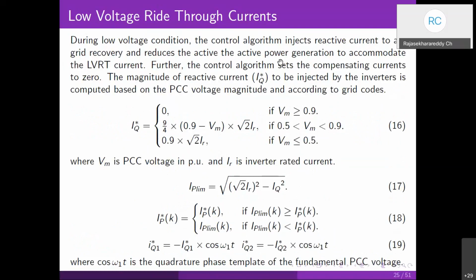Further, during the low voltage period, the control algorithm sets the compensation currents to zero. The reactive current IQ to be injected by the inverters is computed based on the grid codes. Here, if the grid voltage magnitude is greater than 0.9 pu, this reactive current component, the LVRT current of the voltage source inverter, will be set to zero.